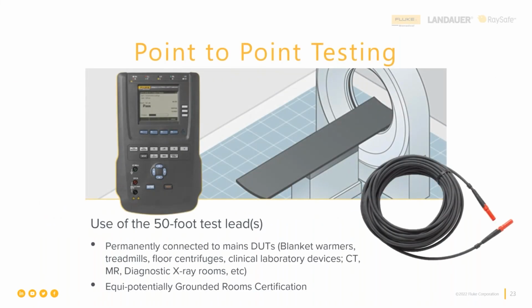Well, what about big iron or other things like treadmills or floor centrifuges that may be permanently connected to mains power, or trying to do a test on an equipotentially grounded room or treatment location, where a dedicated ground runs from that room all the way down to a rod that is driven into the ground, so that ground serves only that treatment area, and all metallic conductive surfaces are connected to that ground. So equipotential grounding throughout the room. And so the tests you need to do for that include voltage, resistance, and current tests for each location.